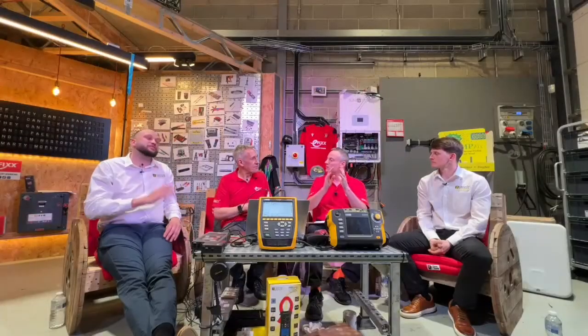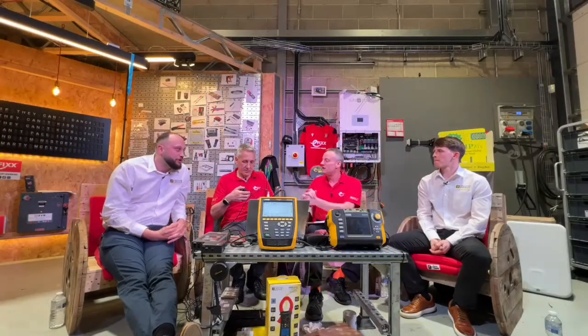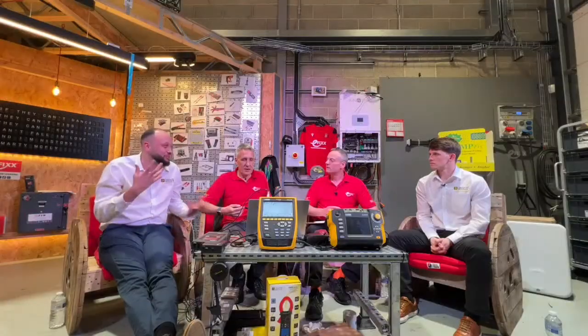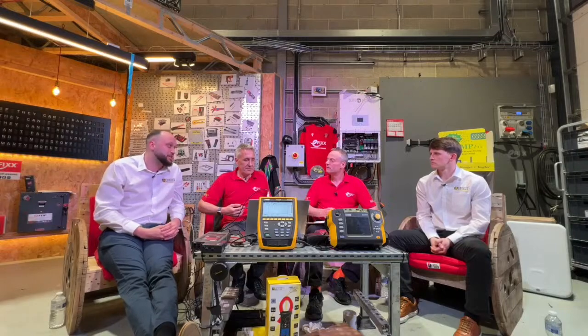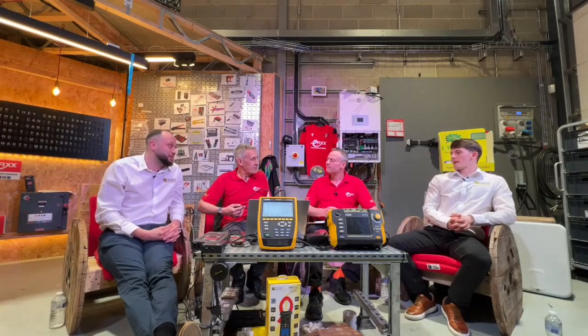We've got the 50 hertz cycle, but not everything is working at 50 hertz, and that causes us an issue. Various different loads ultimately aren't at that fundamental frequency - it's down to switch mode power supplies, variable speed drives, stuff that isn't drawing sinusoidal currents in line with the voltage at 50 hertz. If the current is switching on and off across the cycle, we can have stuff drawing not at the fundamental frequency, and it can cause issues.